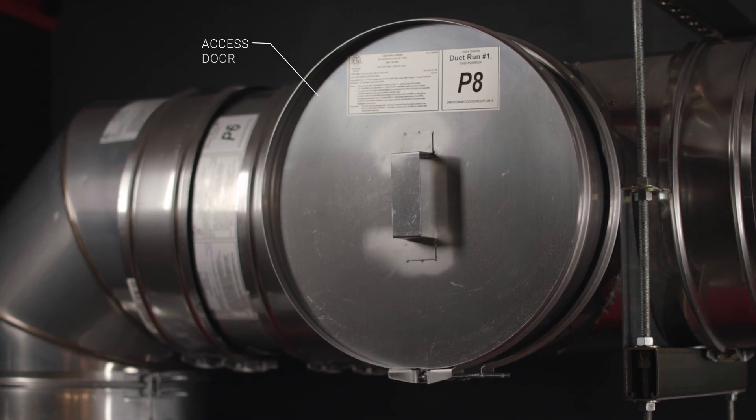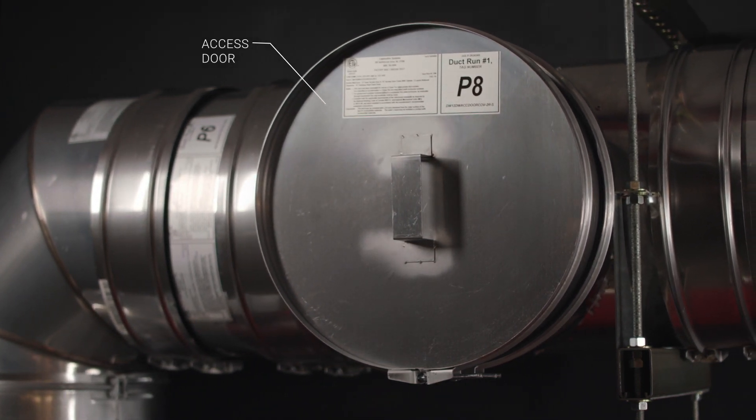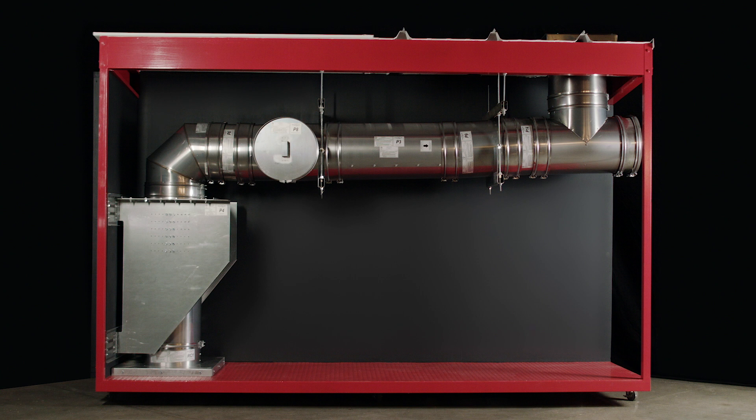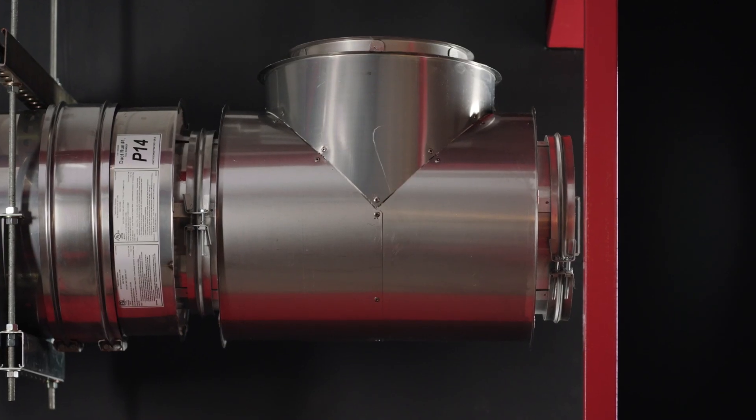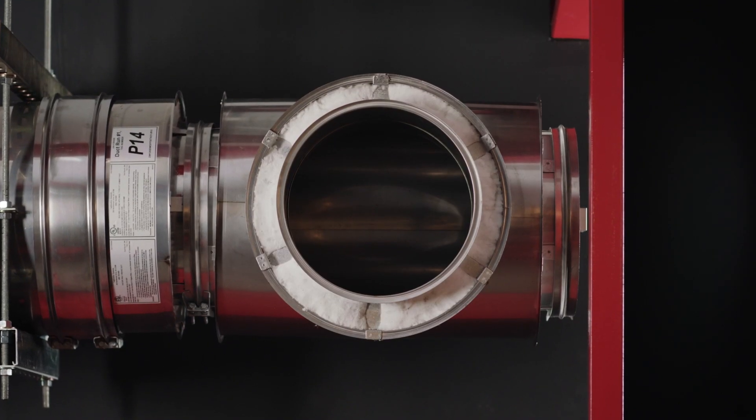Access doors or clean outs are required on all grease ducts for proper cleaning and fire prevention. The location of the access door can be found in your installation drawings. All access doors must be positioned on the top or side of the duct run.